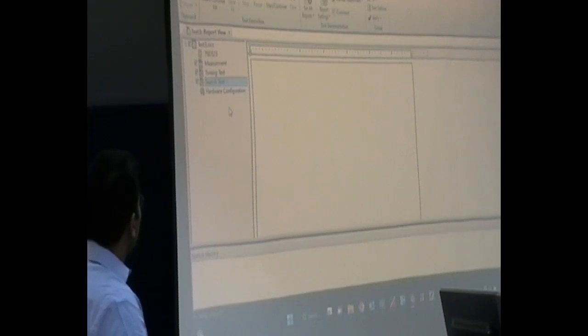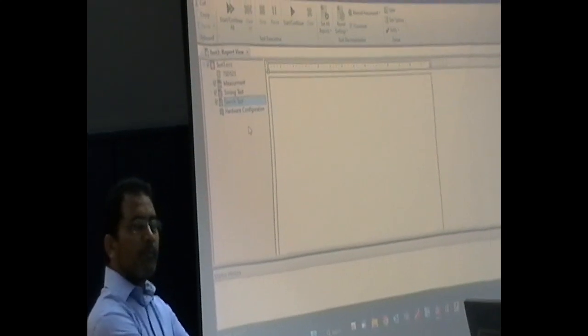And the search test. Usually the search test will be done maybe at the beginning, once I'm changing the setting, because I want to make sure that my setting is correct. Basically, the search test is testing the reach of the relay. We've made some setting for reactance and resistance, and we want to make sure whether it's exactly reaching this impedance or not. I'll start with the measurement first.